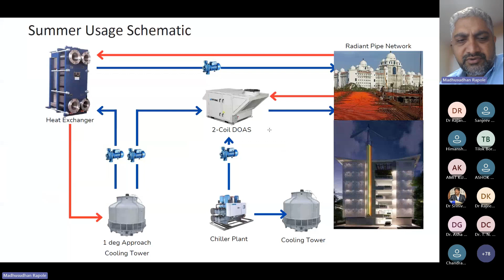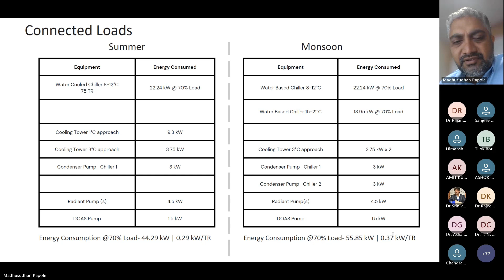In monsoon, since we are not able to get the required temperature from the cooling tower, the second chiller is also used, but at a very high elevated temperature. Even in that case, you are able to get around 0.37 kilowatt per ton.